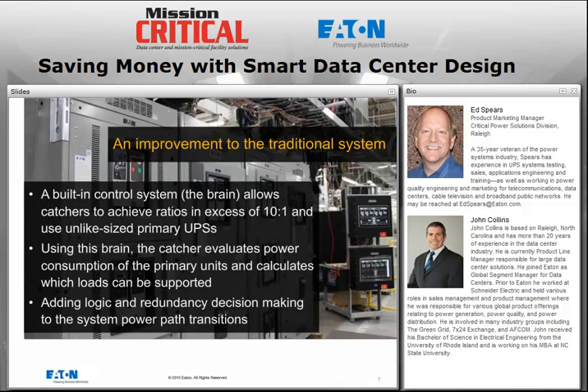And Ed, I'll just add one comment to that. Remember that UPSs typically operate most efficiently when they're close to full load, and there's been some adjustment to that over time as manufacturers realize that full load really isn't the optimal target. But that catcher UPS, the reserve UPS, when it's not being utilized, is at 0% load. It's kind of like driving a car at a red light. When you're stopped at a traffic light, you're getting 0 miles to the gallon. Same situation there. When that reserve UPS doesn't have any load on it, it's operating in its most inefficient manner.